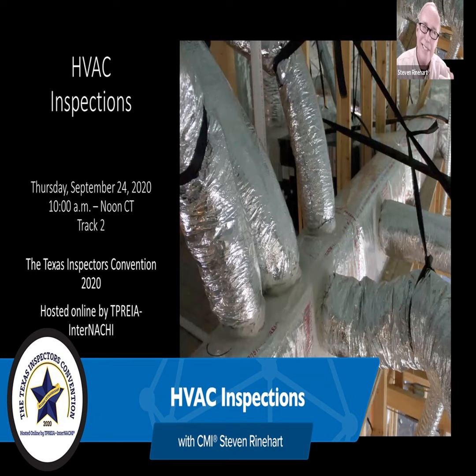Nothing worse than finding one of these puppies they put up in the attic. They did it during renovation when the sheetrock was down, and there's maybe a way to scuttle in there to the attic to inspect it. There's no way to get that thing out if they had to replace it. And remember, we're talking the biggest component is the air handler. The other parts you can take apart. So you need that air handler to be able to get down and out. And we're not talking a little closet scuttle hole. If it's in the attic, I want to see some pull down stairs. Now they may be pulling the stairs out of that rough opening to get that air handler in and out, but basically you can do it.